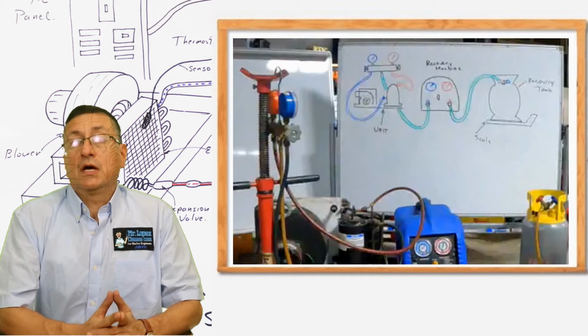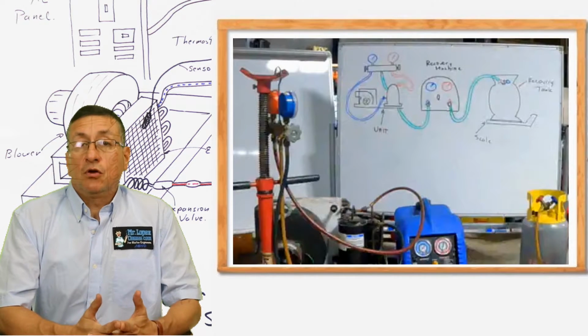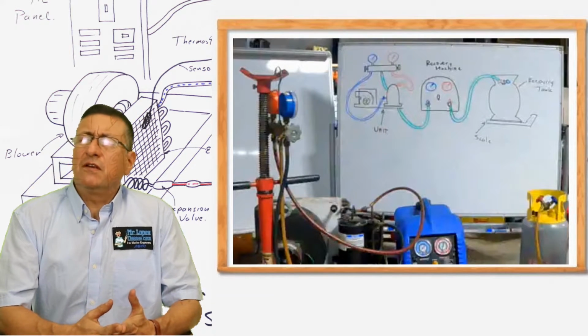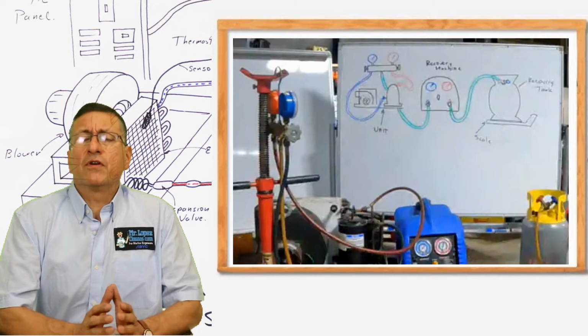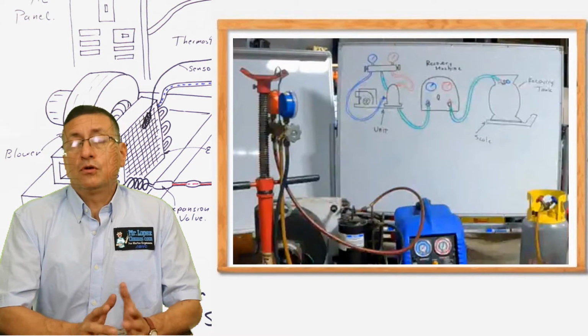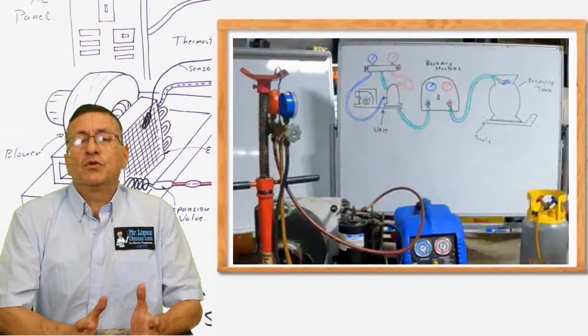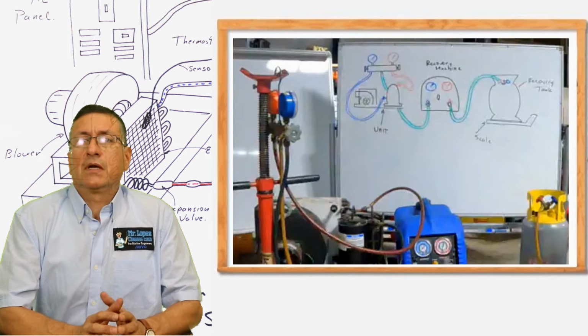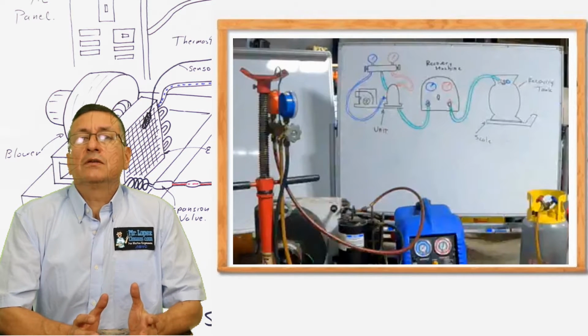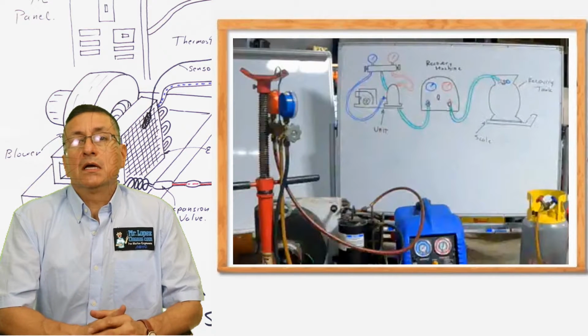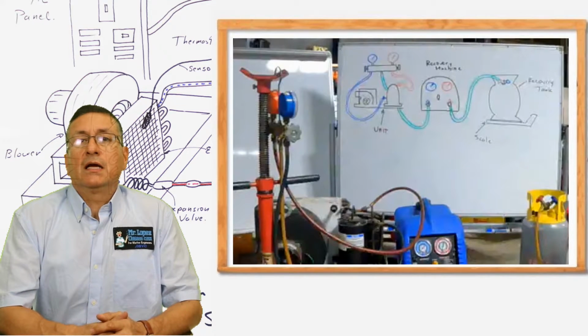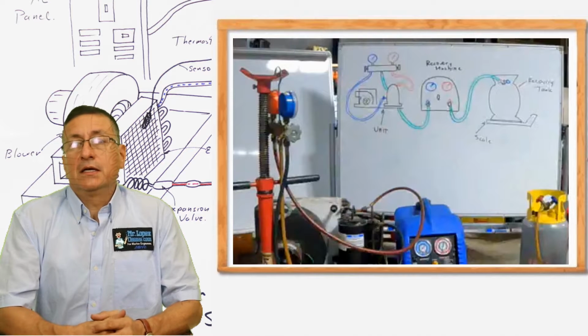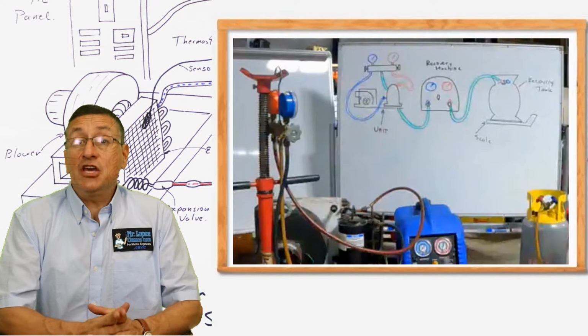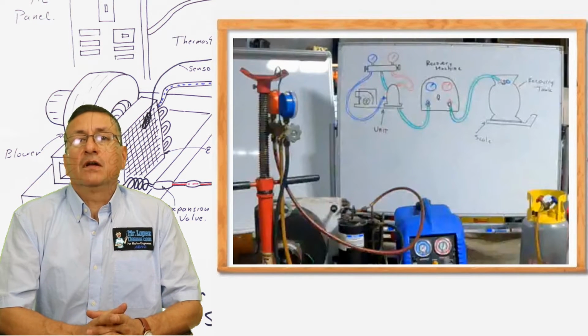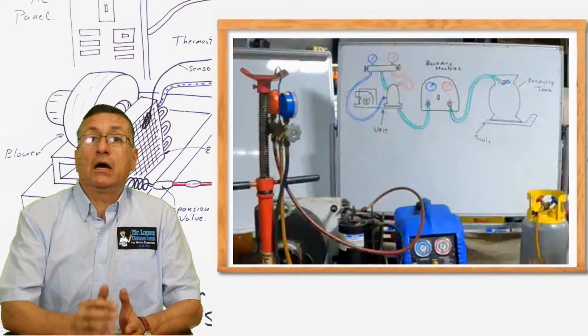Yes, we are going to use a recovery machine in order to explain the procedure, the different types of procedures to recover the refrigerant, and also we are going to do the procedure to pull a vacuum on the system. We are going to analyze the procedure to connect the vacuum pump and to connect the vacuum gauge in order to verify if the vacuum is going down.